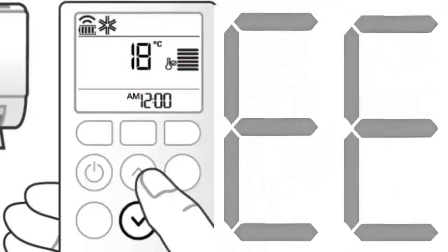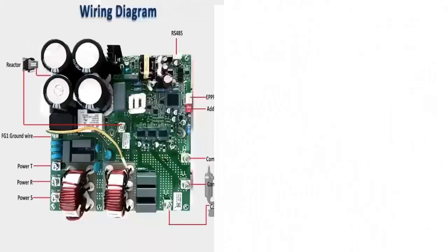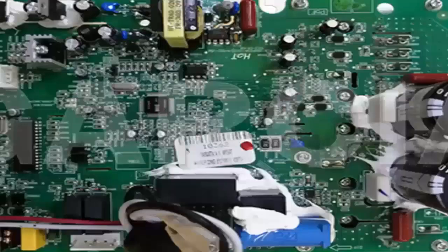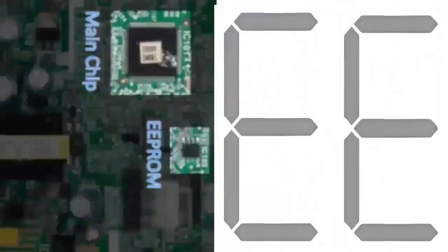2. Observe if the E error appears immediately. In many brands, when the problem is specifically in the EEPROM memory, the unit may change the value or number of the error code multiple times.